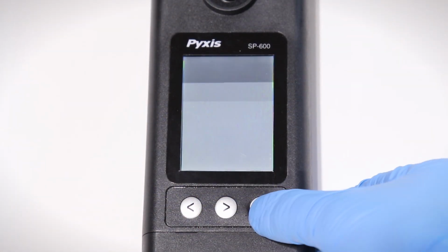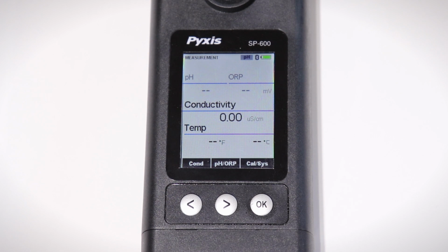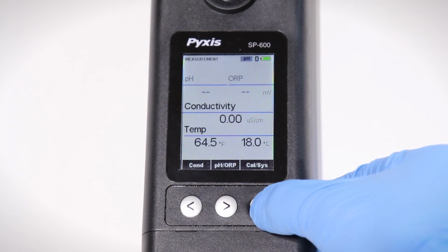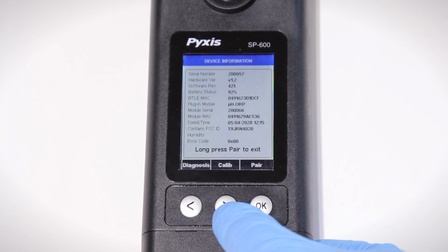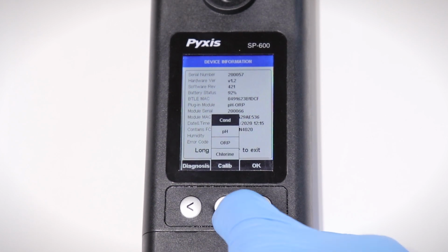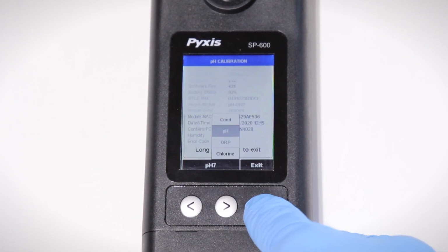Press the OK button to power on the unit. Then press the OK button again to access the Calibration and System Settings menu. Press the right arrow button to select Calibrate, and navigate to pH. Then press the OK button to select pH.